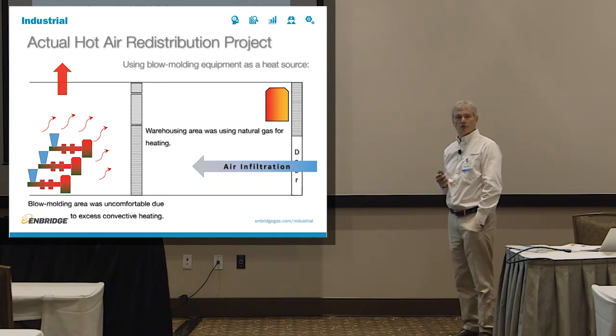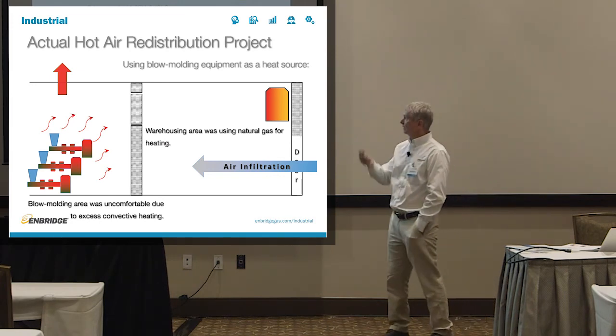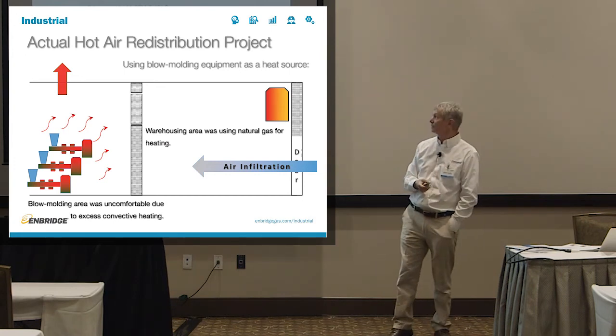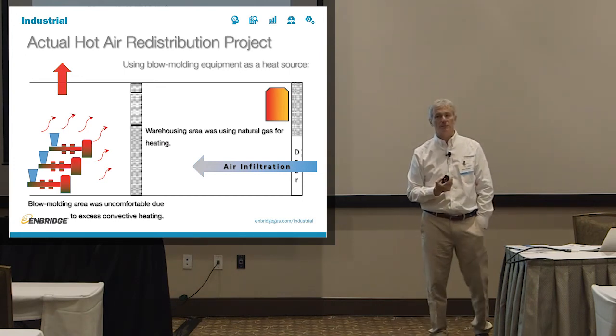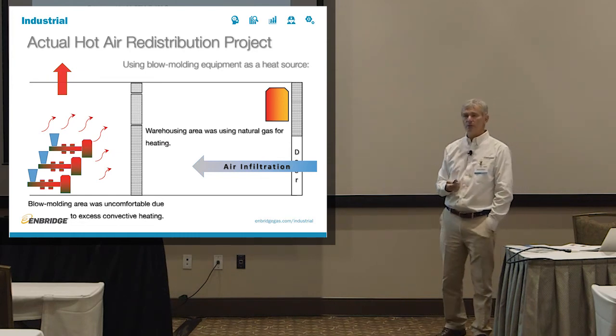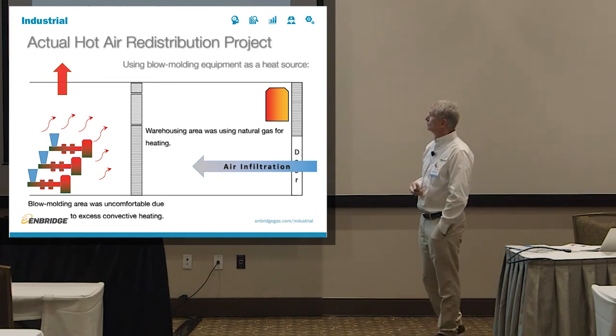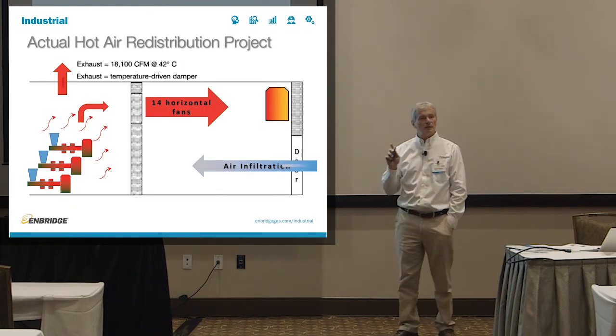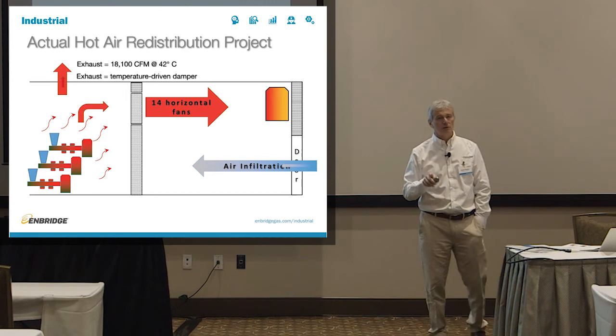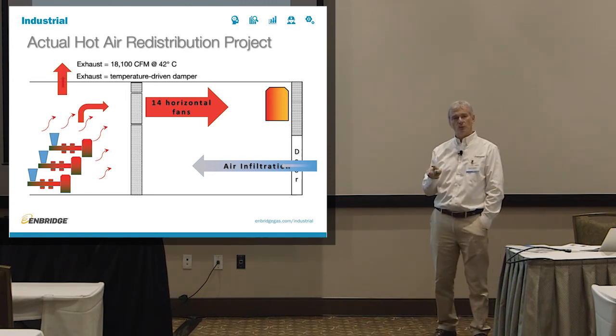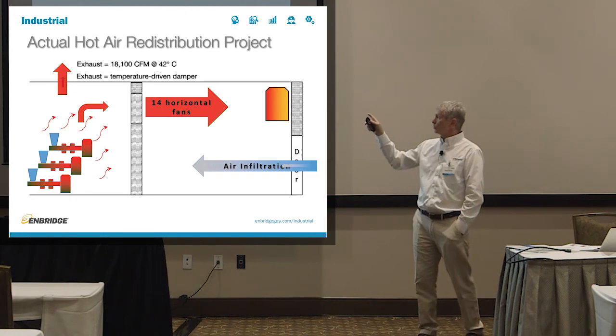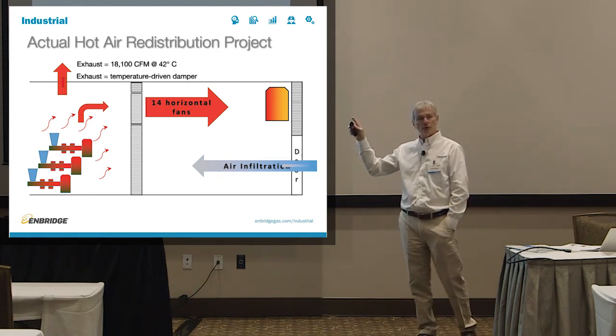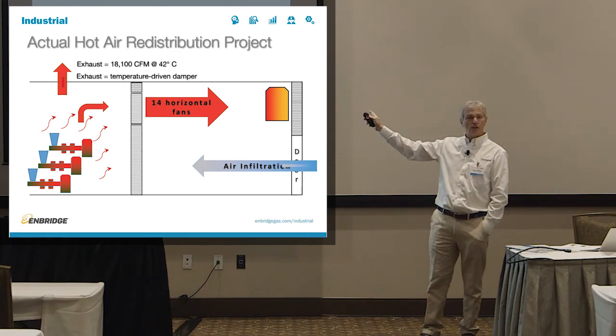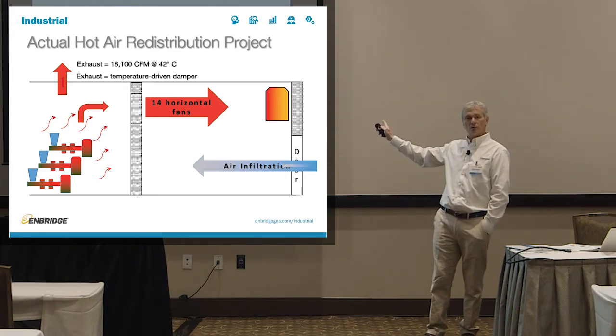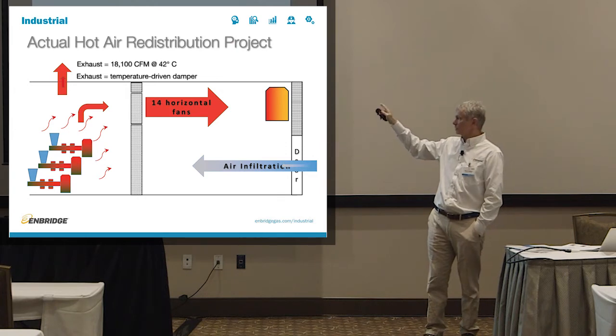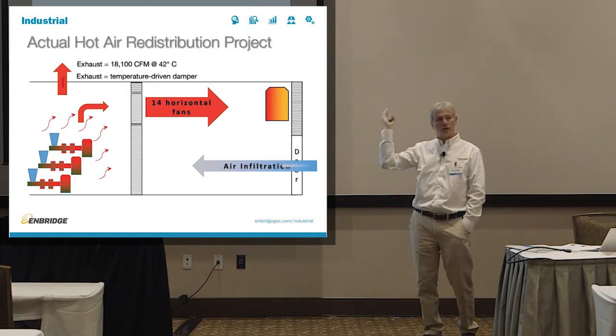George was there. He measured their exhaust, helped them measure it. We had 18,000 CFM of air leaving at about 42 degrees Celsius, believe it or not, out of the facility. That's a pretty hot airstream. So what they did is they put temperature-driven dampers on their exhausts so that when it's cold in the winter months, they installed fans in between two areas that would draw this hot air from the blow molding, and it would dump it into the warehouse. So if I'm not mistaken, they installed something like 14 fans along the huge warehousing wall.